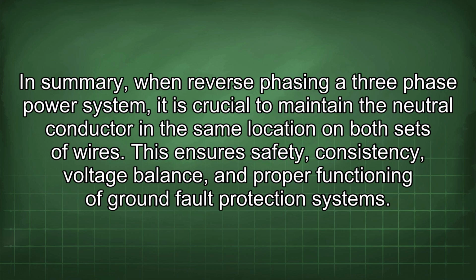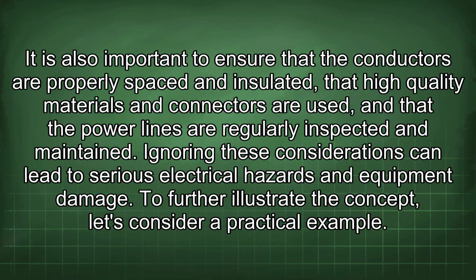In summary, when reverse phasing a three-phase power system, it is crucial to maintain the neutral conductor in the same location on both sets of wires. This ensures safety, consistency, voltage balance, and proper functioning of ground fault protection systems. It is also important to ensure that the conductors are properly spaced and insulated, that high-quality materials and connectors are used, and that the power lines are regularly inspected and maintained. Ignoring these considerations can lead to serious electrical hazards and equipment damage.